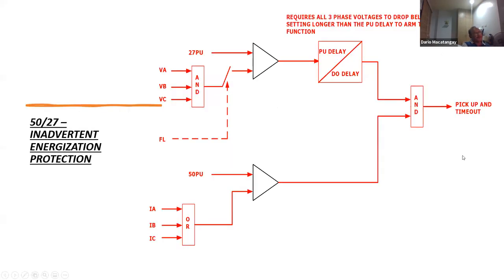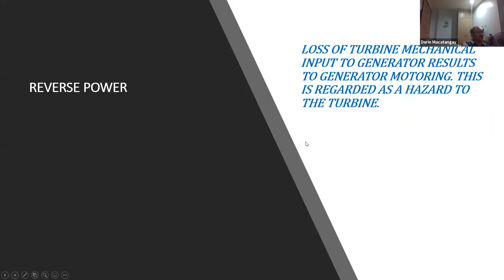This is handled by some kind of logic. We have an arming delay and an arming input, dependent on the voltage. During maintenance, the voltage is low, so it's armed, and there is a one here. The other input here is zero, so one and zero is zero. Now when suddenly the breaker is closed with the generator at standstill, this is armed at one, and you get an input here of one. One and one becomes one, so the relay will pick up. That's your inadvertent energization.